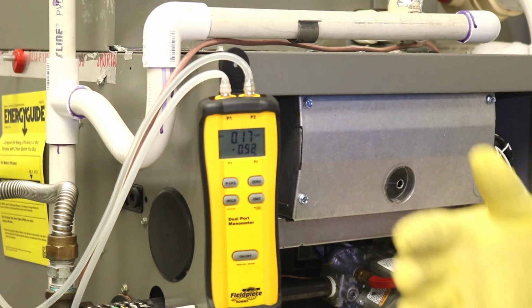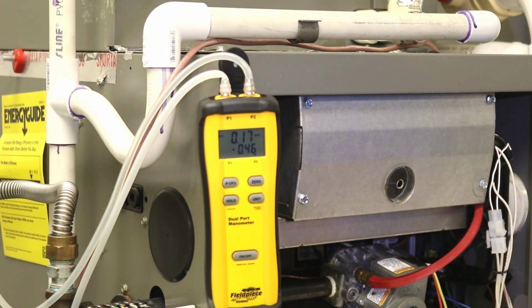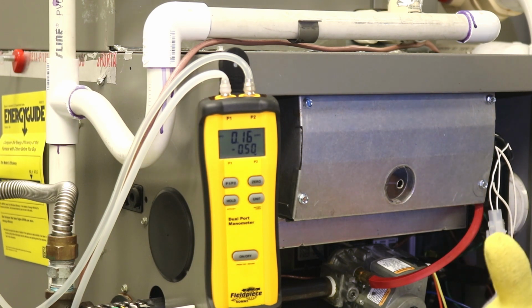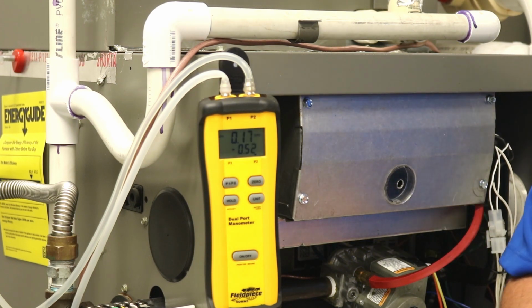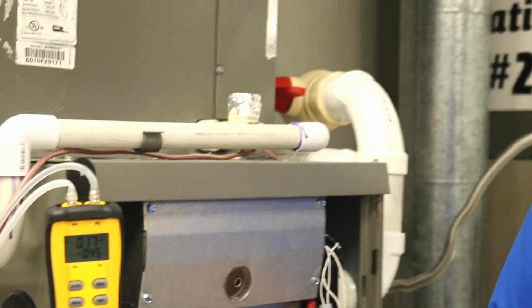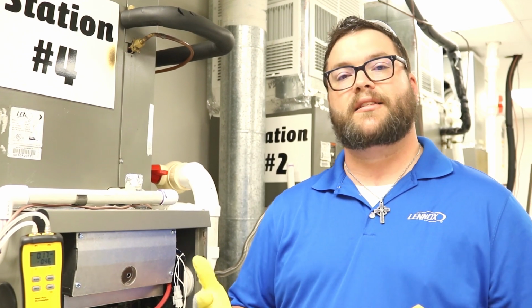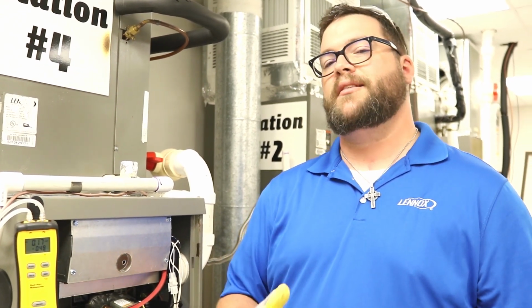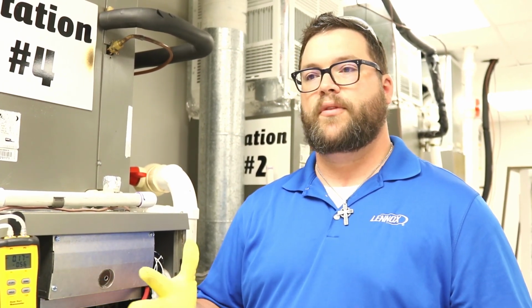So making sure that you know how to check static pressure to verify that it's within that range is very, very important. This is something that when you're doing a maintenance or a service visit, it's very important to be able to explain to a customer, hey, this is what's going on with your system, and this is why I don't believe that your compressor is the problem, or this is why I don't believe that the equipment is low on refrigerant. There are lots of other pieces of the puzzle. Most often, you're gonna find that airflow is a major issue within the HVAC system.